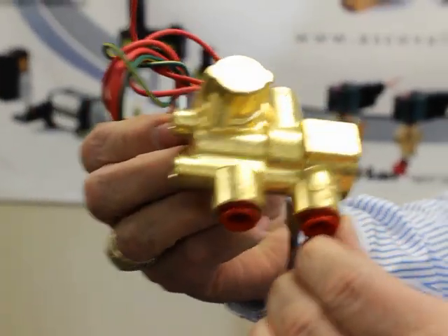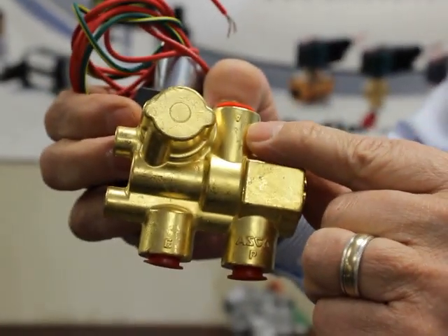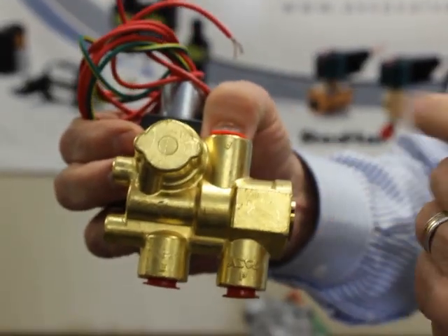On a three-way valve, you may see the pressure port marked with a P, the exhaust port marked with an E, and your line or load marked with an A. If it's a four-way valve, there would be an A and a B.